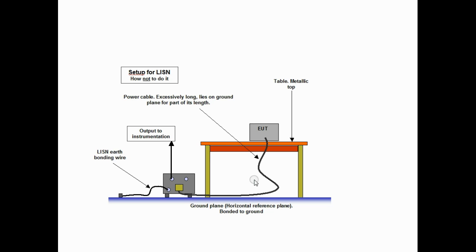This is an example of how not to do it. We do not need a ground plane on the tabletop. The table should not be metallic in any way. The cable should not be excessively long and the LISN needs to be bolted to the ground plane. If we do the bonding via a bonding wire, at the frequencies of interest this wire will present high impedance and therefore is quite unsatisfactory.